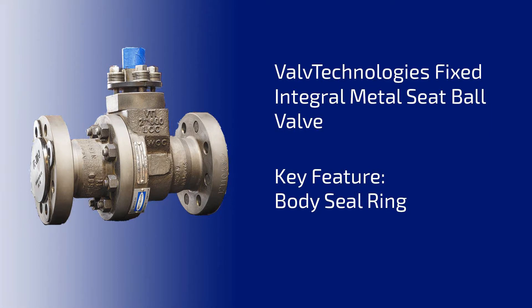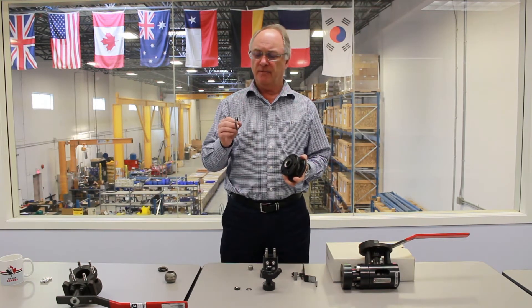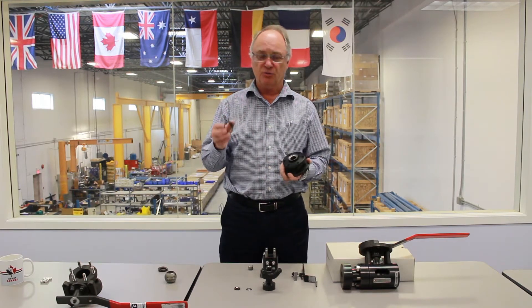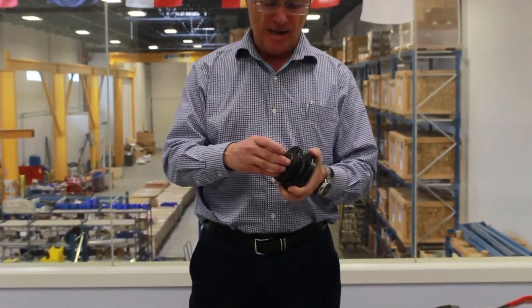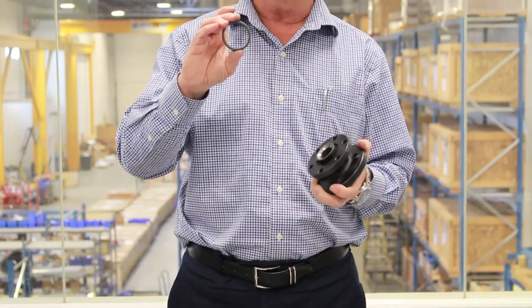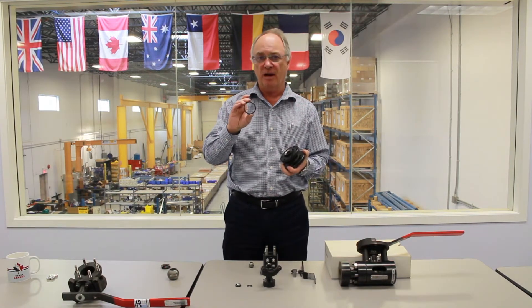Now we're going to look at the body joint gasket. When you're providing a high performance isolation valve with zero leakage, you also don't want any leakage from the body joint or the stem. In the ValvTechnologies V1 series, they use a metal gasket that's trapped inside a slot in one of the body halves and then compressed by the body bolts. This exerts a force of over 20,000 psi and ensures a very tight seal. The gasket is made of either 17-4 pH or Incoloy at higher temperatures. They're graphite loaded, and valves three inch and bigger have a secondary graphite seal as well.